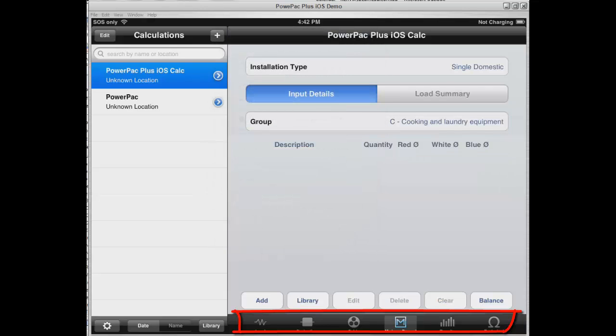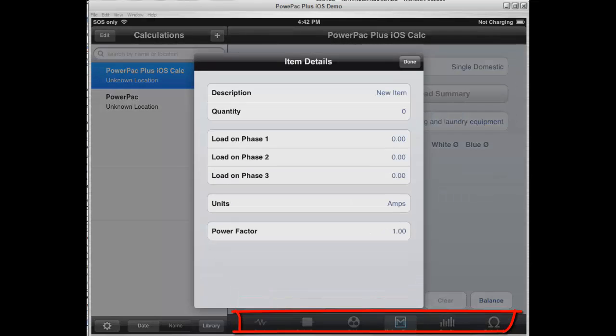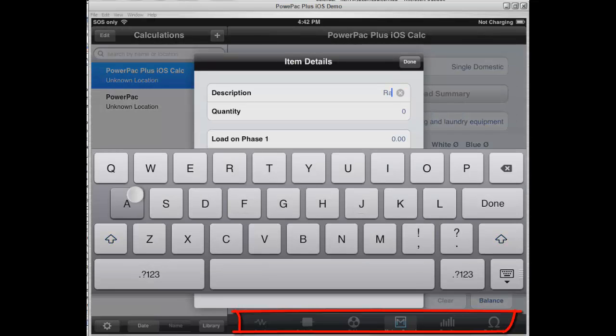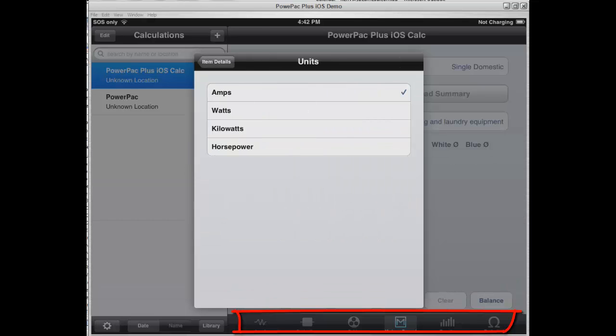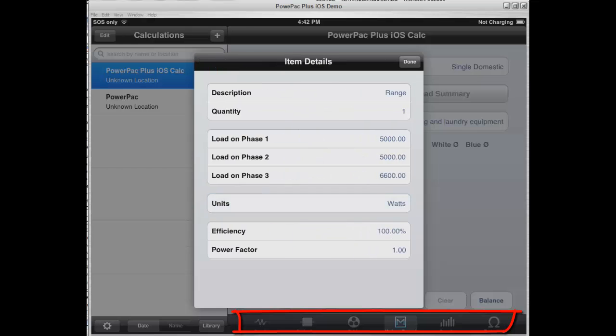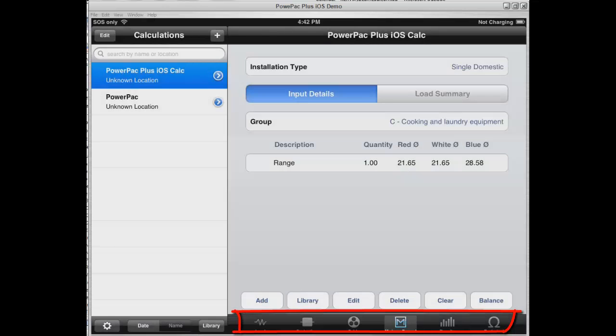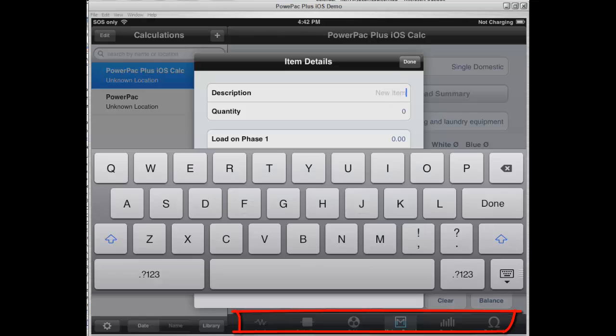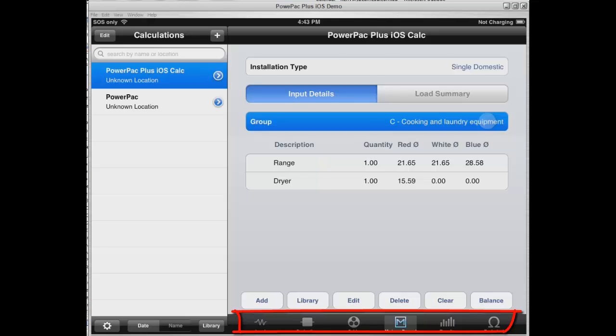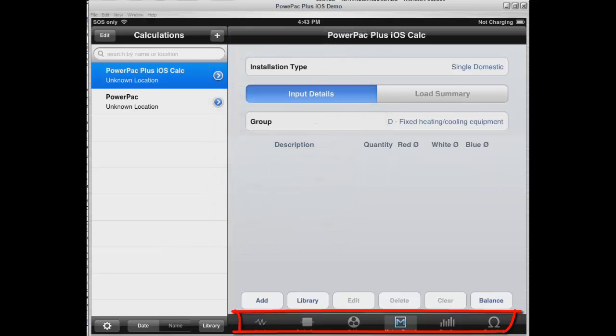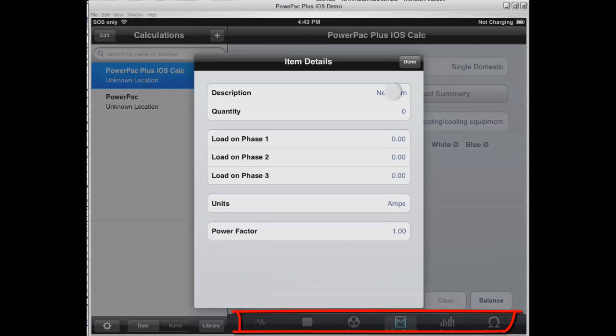We're doing a mixture of adding from the library and adding manually. Here we're going to add a range — we've got one. We're going to split the phases up, same as in the standards. We can select amps, watts, kilowatts, or horsepower, and PowerPak will convert it back to amps. We're now loading a dryer also in load group C, then moving to load group D to add our air conditioner, which we'll do manually.